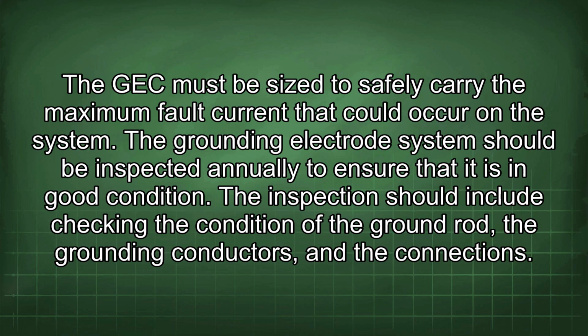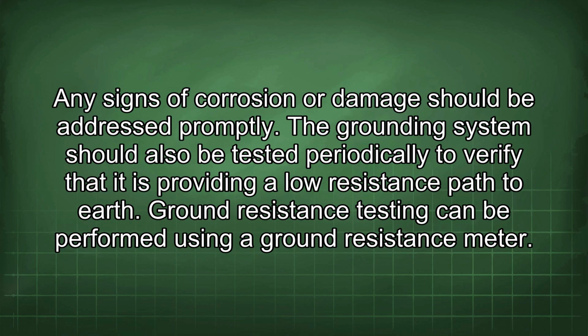The grounding electrode system should be inspected annually to ensure that it is in good condition. The inspection should include checking the condition of the ground rod, the grounding conductors, and the connections. Any signs of corrosion or damage should be addressed promptly. The grounding system should also be tested periodically to verify that it is providing a low resistance path to earth.